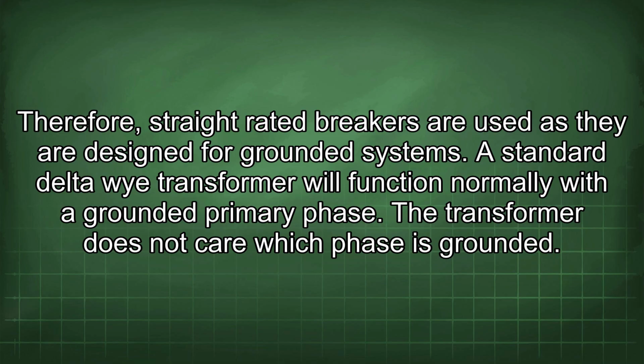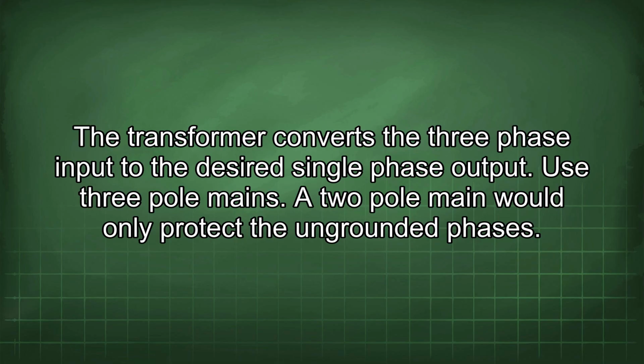A standard delta-Y transformer will function normally with a grounded primary phase. The transformer does not care which phase is grounded. The transformer converts the three-phase input to the desired single-phase output.